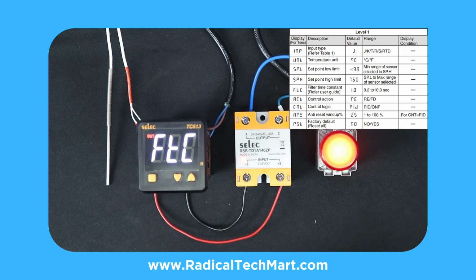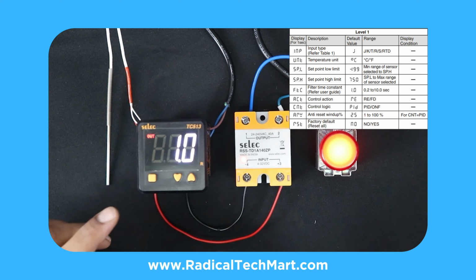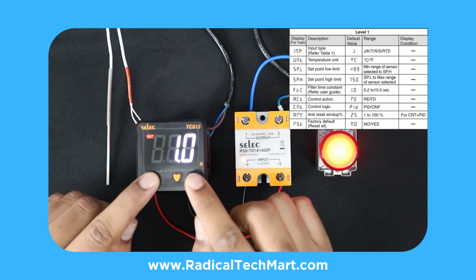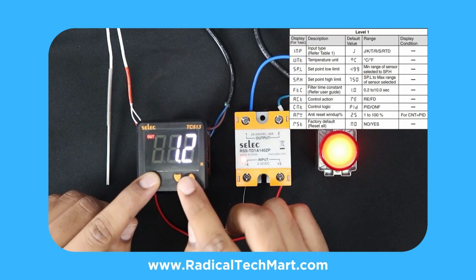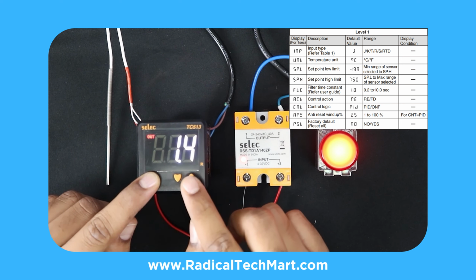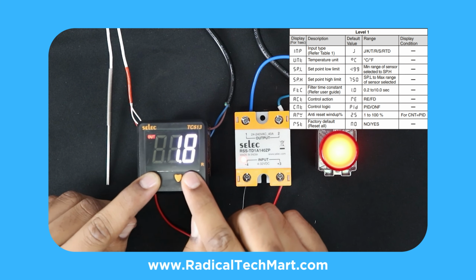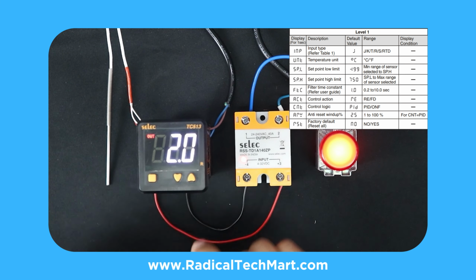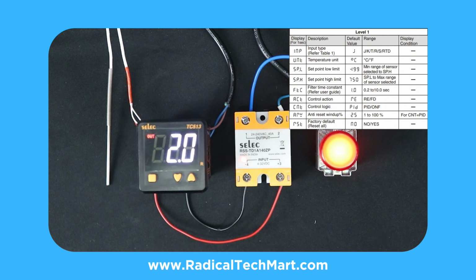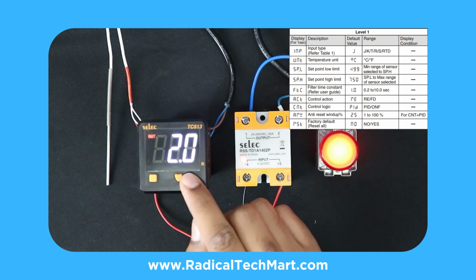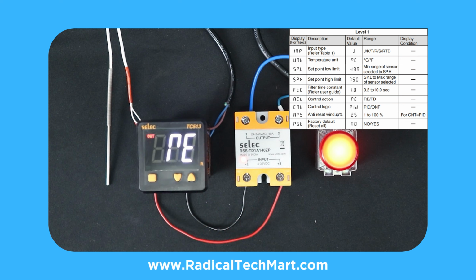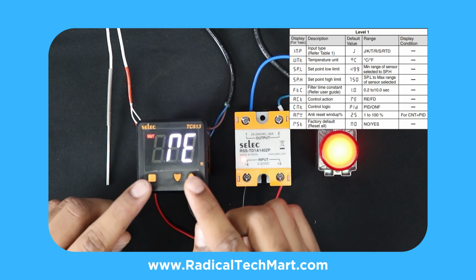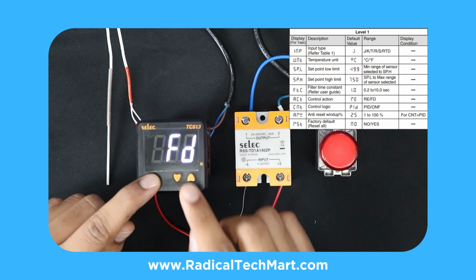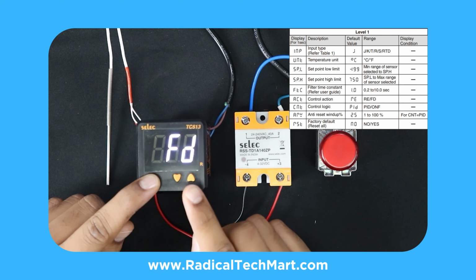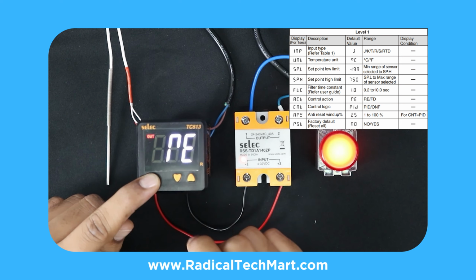The next parameter is filter time constant, which allows the controller to reduce noise from the process application. We can change this value by long pressing the Set key and Instrument key together. After pressing the Instrument key, the unit control mode appears. We can set the control action to reverse mode or forward mode. Reverse mode is used for heating applications and forward mode is used for cooling applications.